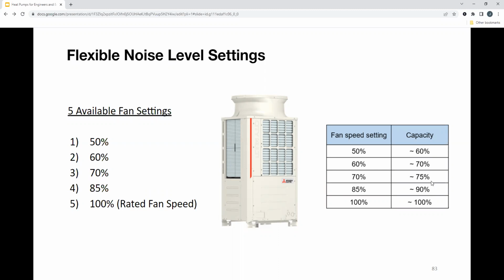So it reduces the capacity as well, right? In the instance where 70% fan speed is enough to get to your sound ordinance level, but I need 90% capacity at night for whatever reason, then you can set certain priorities. You can do capacity priority, which ramps the fan back up, gets the capacity you need, and then turns back to that fan speed setting. Or you can do sound priority, where it just reduces the capacity and it just takes a longer time to heat or cool a space. So this is an option that heat pump manufacturers have that you can set up.